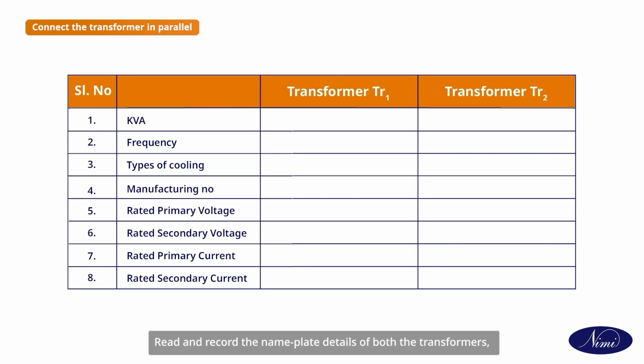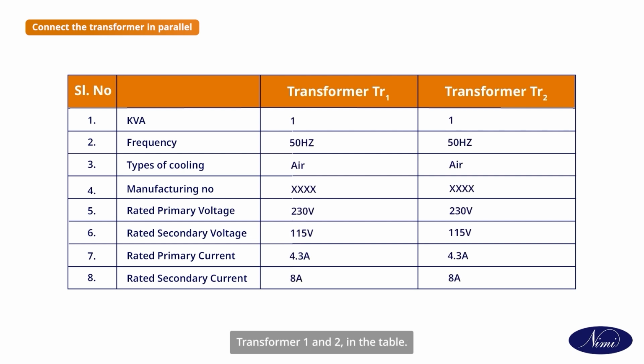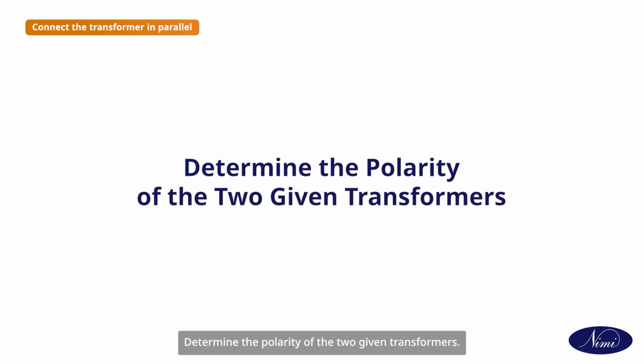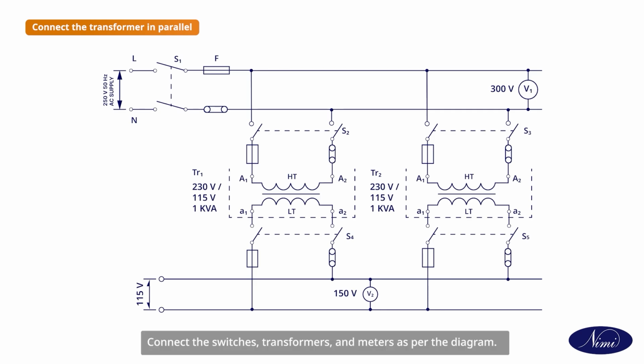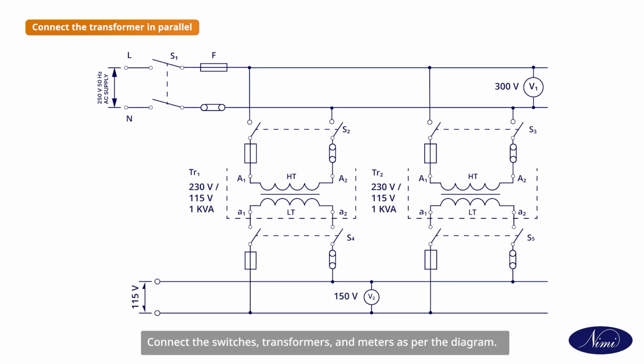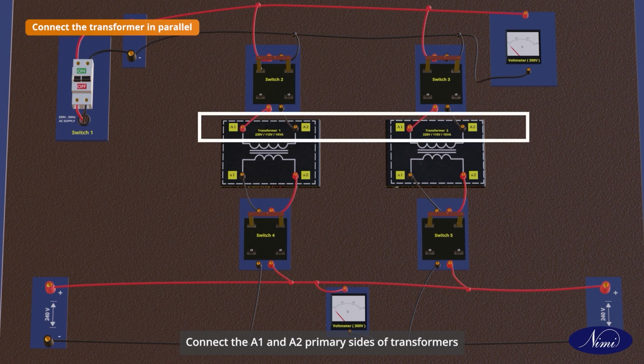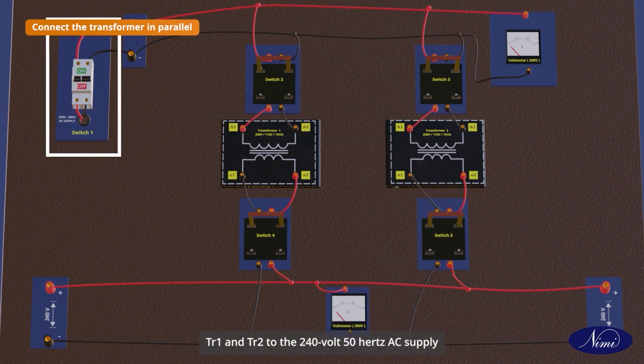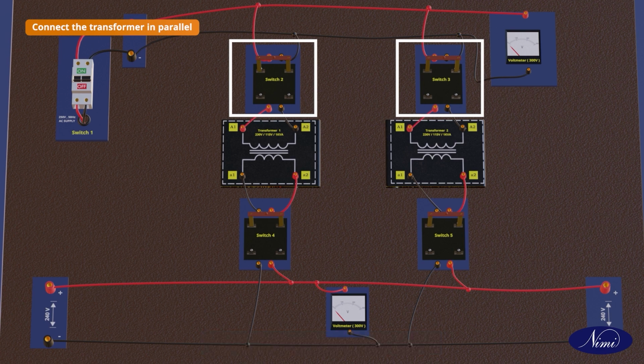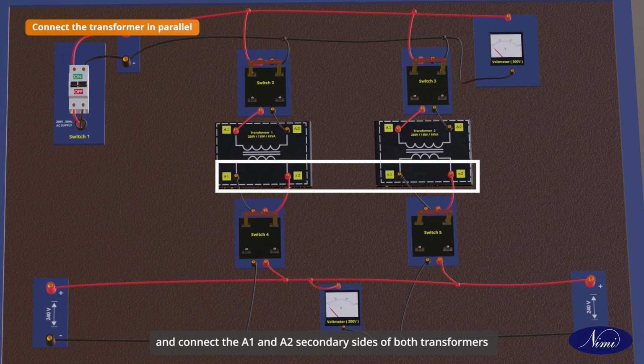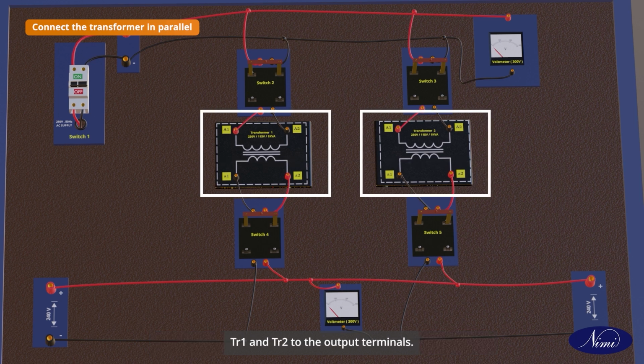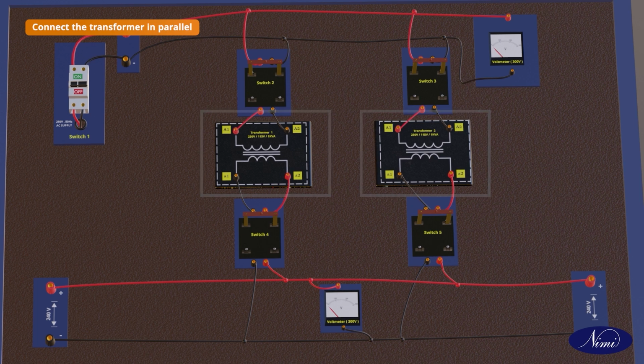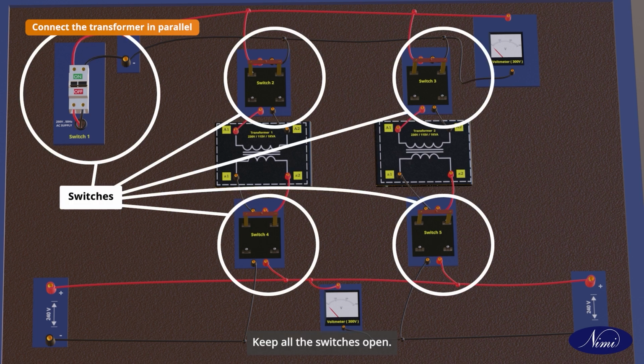Read and record the nameplate details of both the transformers, transformer 1 and 2, in the table. Determine the polarity of the two given transformers. Connect the switches, transformers and meters as per the diagram. Connect the A1 and A2 primary sides of the transformers TR1 and TR2 to the 240 volt 50 Hz AC supply through the switches S2 and S3 respectively. And connect the A1 and A2 secondary sides of both transformers TR1 and TR2 to the output terminals. Keep all the switches open.